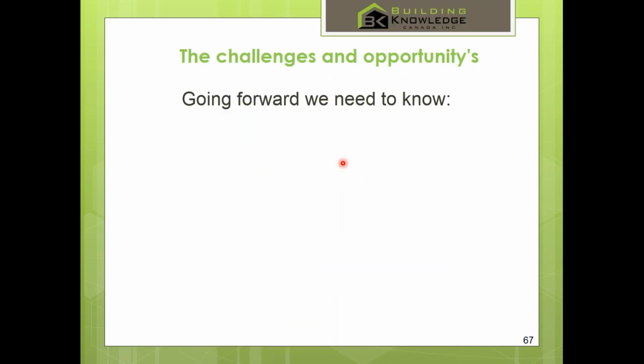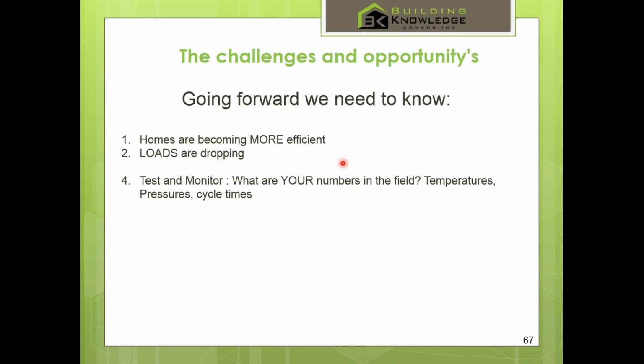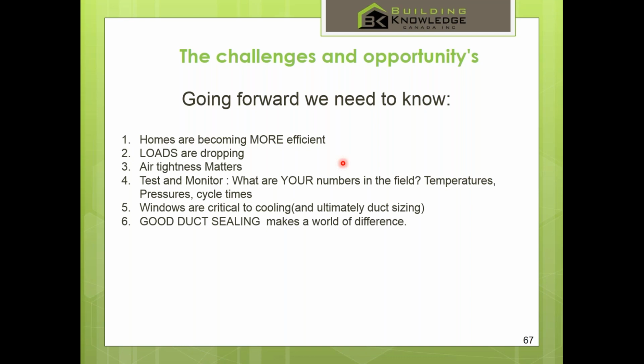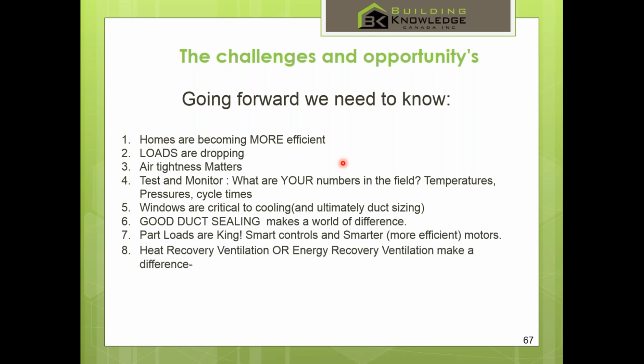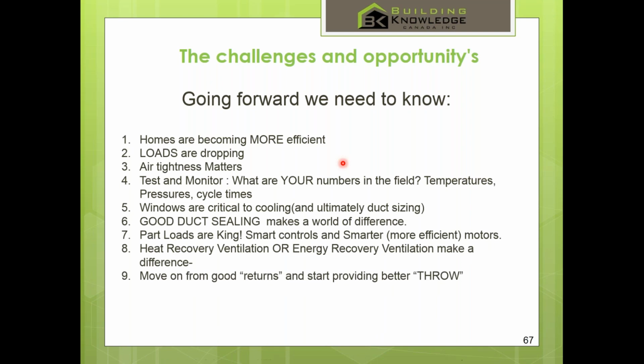So beyond this, going forward, a couple of things you're going to need to know. Houses are more efficient, loads are dropping. Make sure you test and monitor. Know what your air change rates are in the house. Know your blower door values. Know what your cycle times are in some of your furnaces. It takes a good certified energy evaluator less than half an hour to figure this stuff out. You know that windows are critical to the size of your ductwork and solar heat gain. Air tightness matters. Good duct sealing is going to make a world of difference. Part loads are king. Heat recovery, now you're getting credit for it, and start to move on from just having good returns to actually having good registers and diffusers where you actually get throw, heating the home well through diffusion.